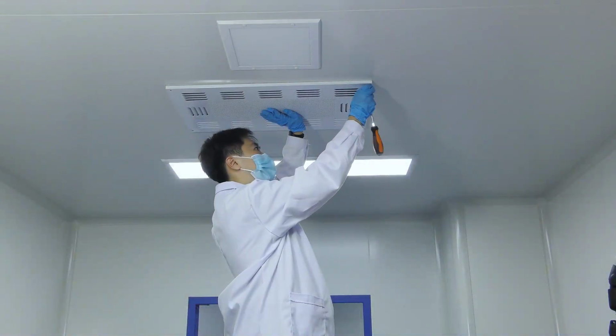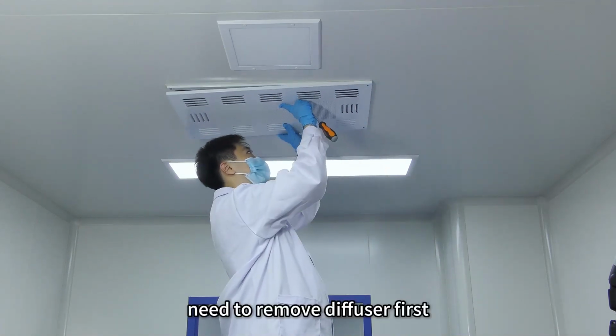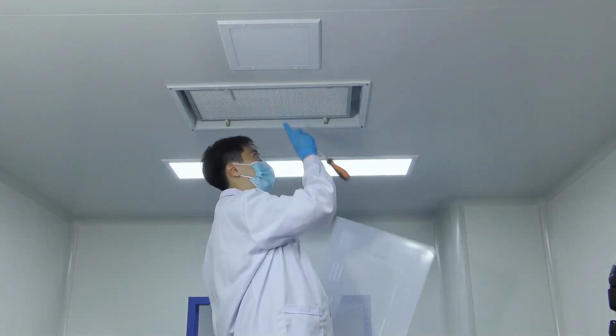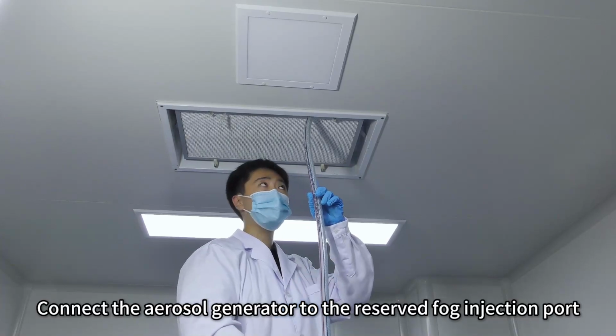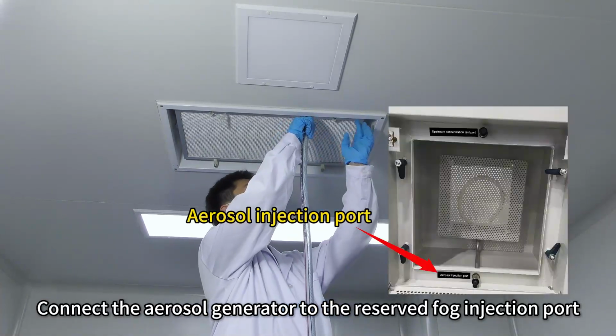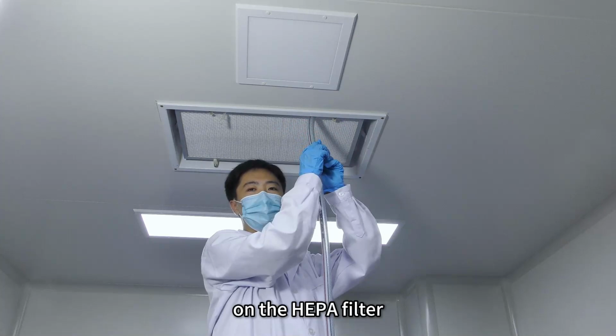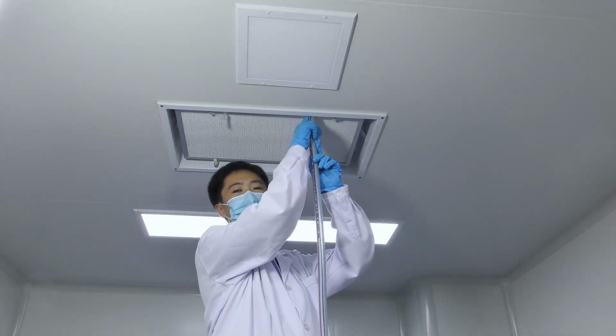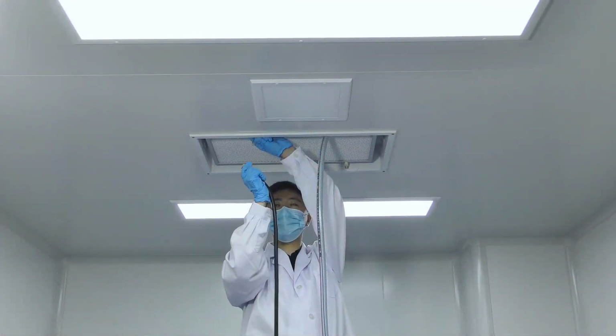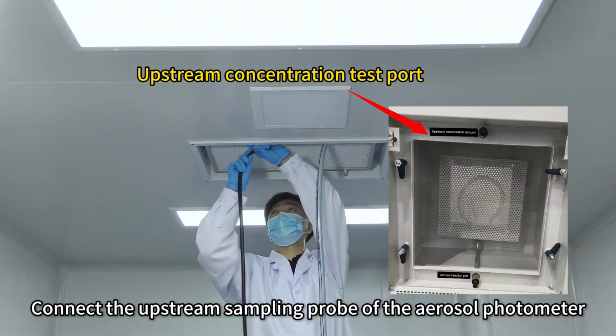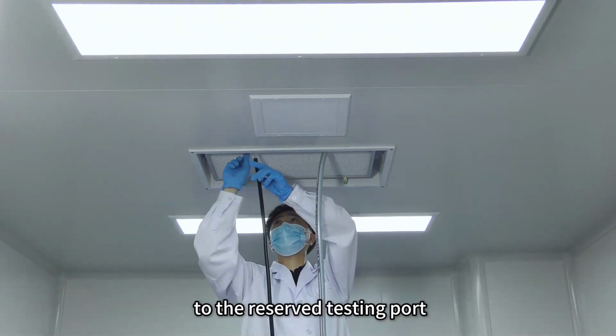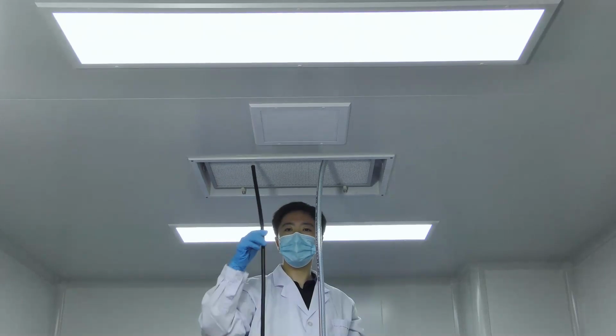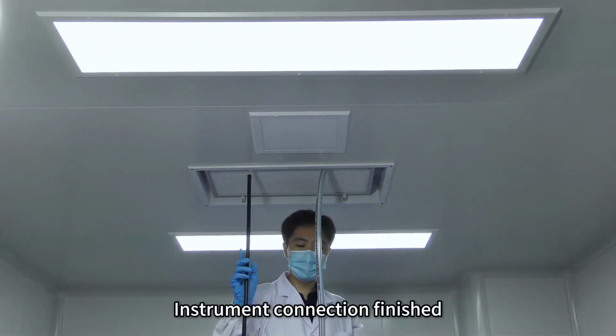Before leak test, need to remove diffuser first. Connect the aerosol generator to the reserved fog injection port on the HEPA filter. Connect the upstream sampling probe of the aerosol photometer to the reserved testing port. Instrument connection finished.